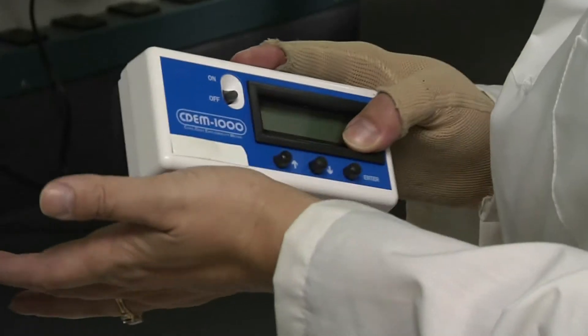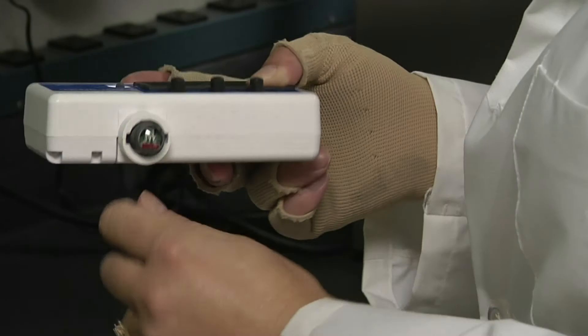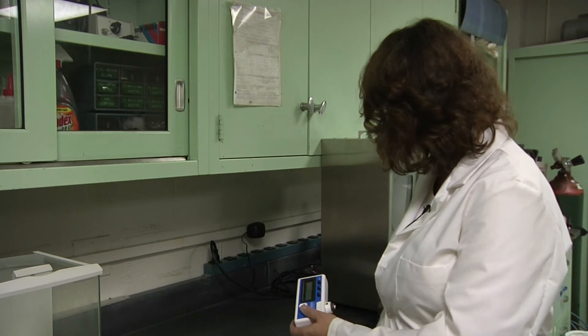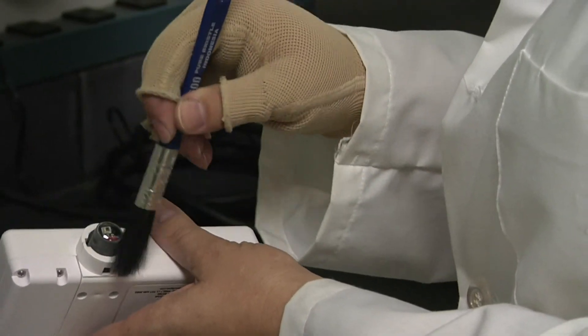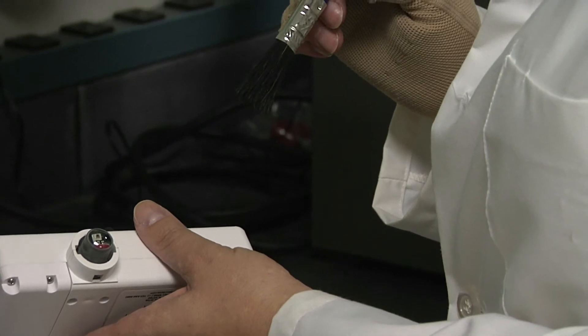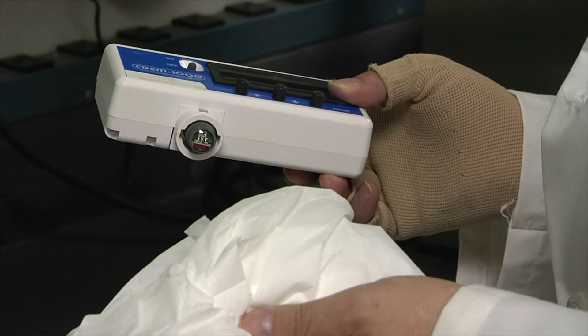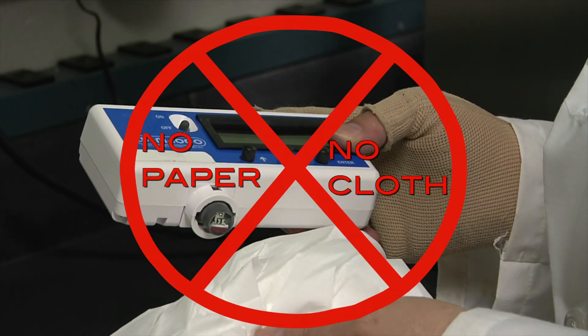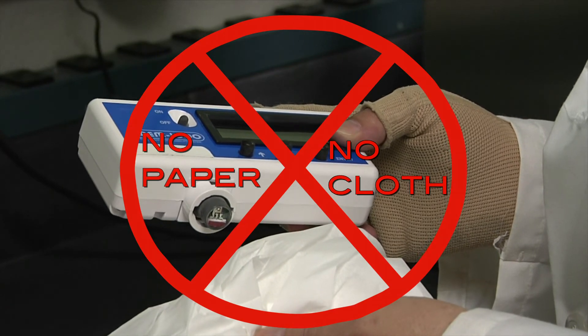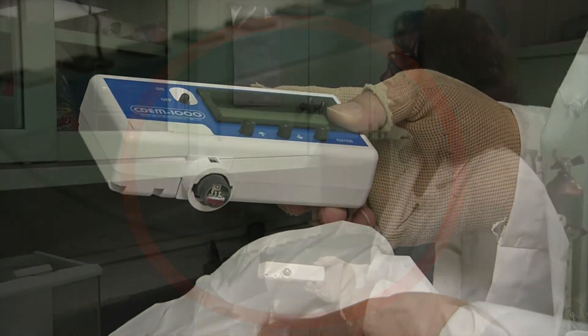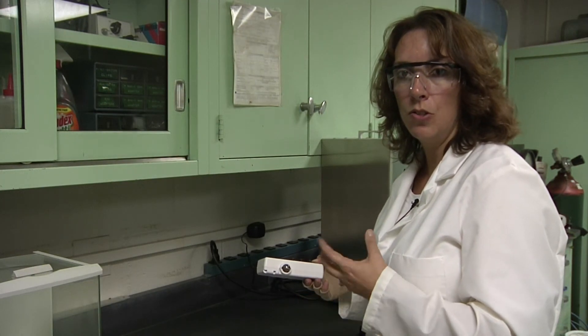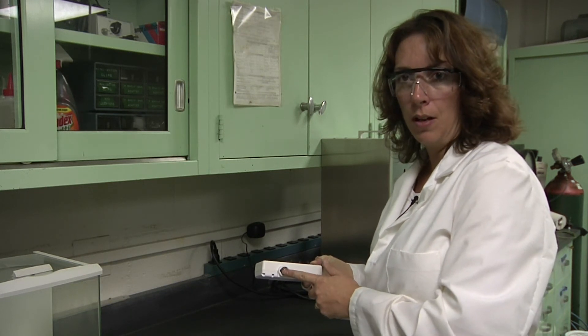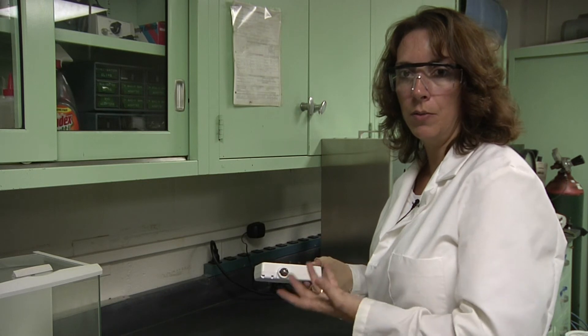To clean the probe, you can use the palm of your hand to wipe any dust off. Make sure there is no dust in and around the probe. You can use your brush to clean that area also. You don't want to use any paper or cloth because that could statically charge the lens and attract either rock dust or coal dust to it preferentially, and that will give you a false measurement. You also don't want to use soap or some type of cleanser because it might leave a film on the probe and give you an incorrect measurement.